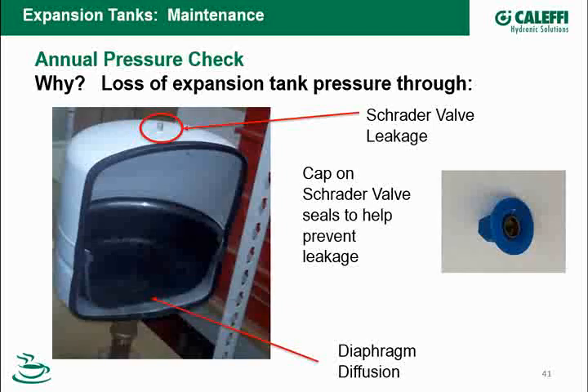Okay? Now, the other place that the tank can lose pressure is directly through the diaphragm. Just as oxygen can diffuse through PEX tubing, depending on the blend of the diaphragm, the thickness of the diaphragm, and how it's cured, the air, particularly the oxygen part of air, has the ability to readily diffuse through that diaphragm, so you will see a bit of it passing through the diaphragm itself into the system. Most manufacturers will tell you that on average expansion tanks probably lose a half a pound of pressure on an annual basis. So it does have to be checked and it does have to be adjusted.